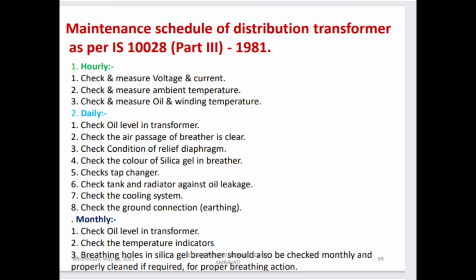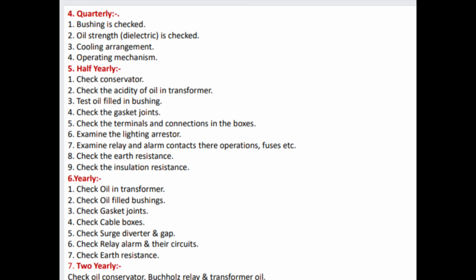In monthly, check oil level in transformer. Check the temperature indicator. Breathing holes in silica gel breather should also be checked monthly and properly cleaned if required for proper breathing action. So, in quarterly, bushing is checked, oil strength, cooling arrangement, operating mechanism, and in half yearly, means 6 months. Check conservator. Check the acidity of oil in transformer. Test oil filled in bushing. Check the gasket joints. Check the terminals and connection in the boxes. Examine the lightning arrestor. Examine relay and alarm contacts, their operations, fuses, etc. Check the earth resistance. Check the insulation resistance. And in yearly, check oil in transformer, check oil filled bushing, check gasket joints, check cable boxes, check surge diverter and gap, check relay alarm and their circuit, check earth resistance. And last is 2 yearly, check oil conservator, Buchholz relay and transformer oil.